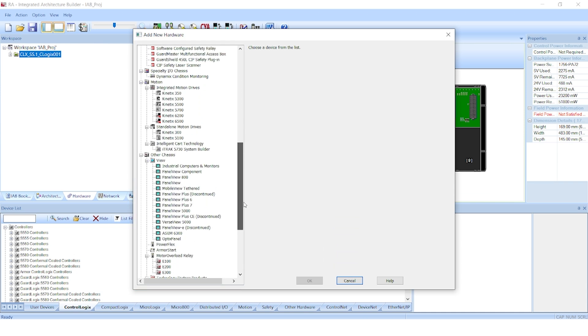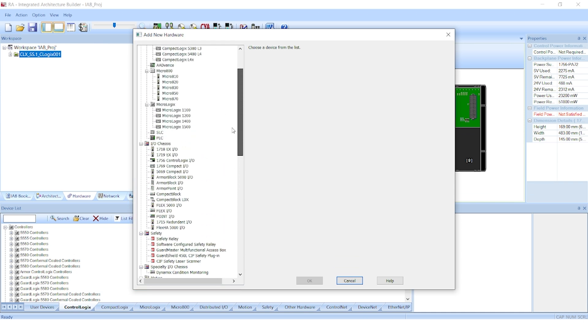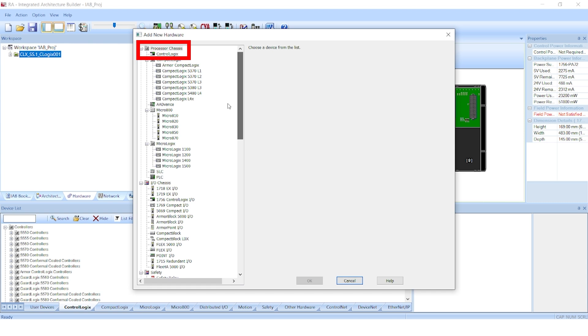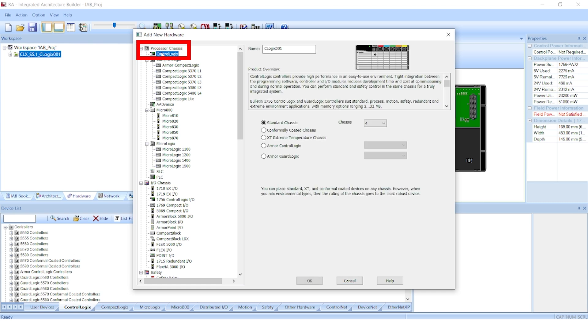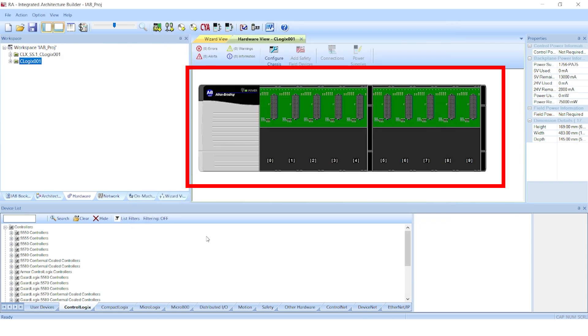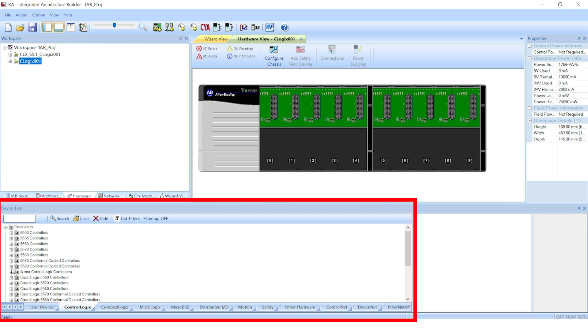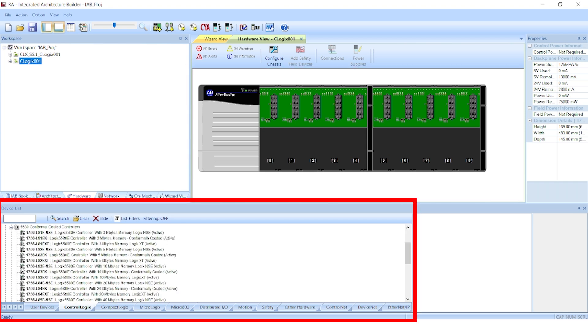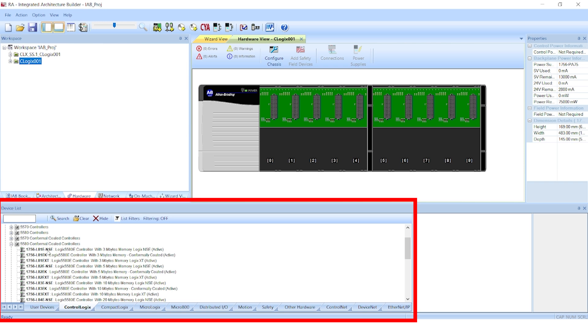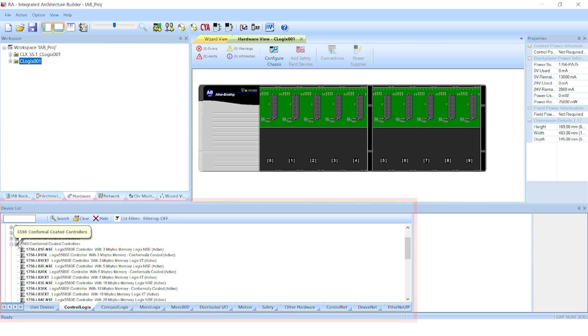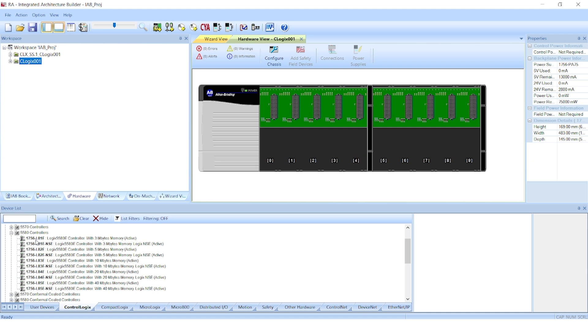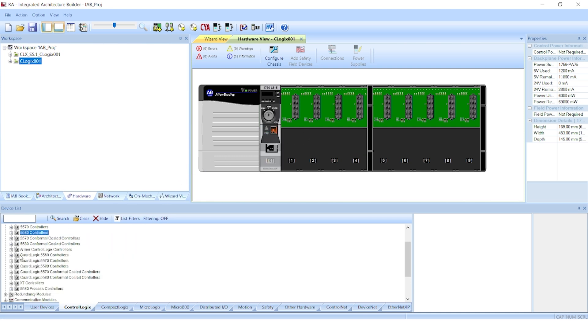In our case here, we're going to select a ControlLogix chassis. I have to select everything, so in our example here, I'll select the 10-slot chassis. IAB generates an empty 10-slot chassis for me to populate with modules. In the lower left corner is a window, Device List, which provides all the available ControlLogix modules for me to select from to build my system. The difference between the wizard and this is that I have to know what I'm looking for. Now I just go through and drag and drop modules into the chassis.